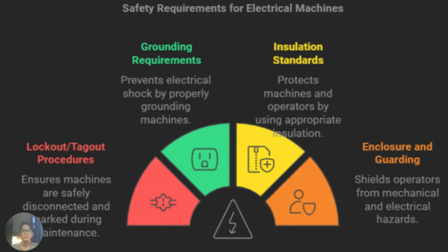Next, for grounding requirements, proper grounding is highly recommended to avoid electrical shock or fires. The NEC has extensive guidelines for the grounding of machines that operate with both AC and DC. AC machines must have a neutral conductor grounded to limit shock hazard, and DC machines are grounded either through their frames or at a grounding conductor.